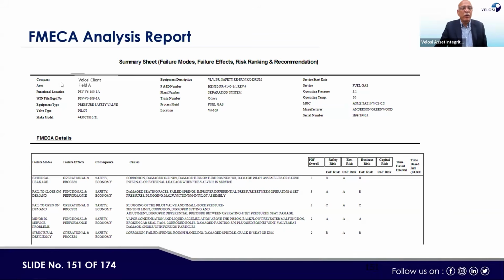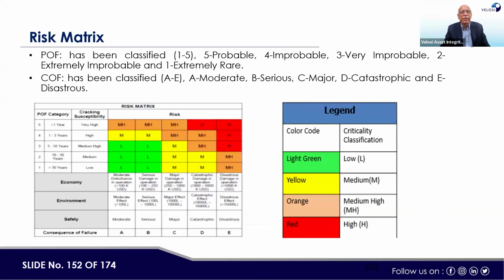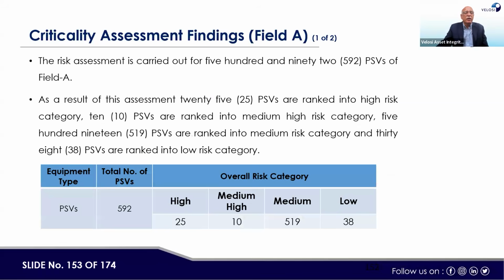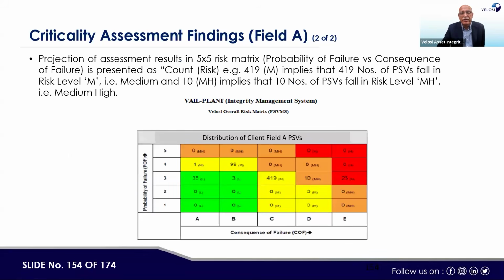So this is the end result where we have the failure mode, failure effect, then consequences, causes, then POF overall, safety risk, environmental risk, business risk, and capital risk. This is the FMECA analysis of that particular PSV. And this is the end result, what the POF, COF, and where we stand. So here, in general, we found that the total number of PSVs in high risk is 25, medium high 10, medium 519, low risk 38. So high and medium high are 25 and 10, meaning 35. Then this is the distribution of those PSVs from a risk point of view, 419 were coming here. This is the number. Then 335, the various distribution in the risk matrix.